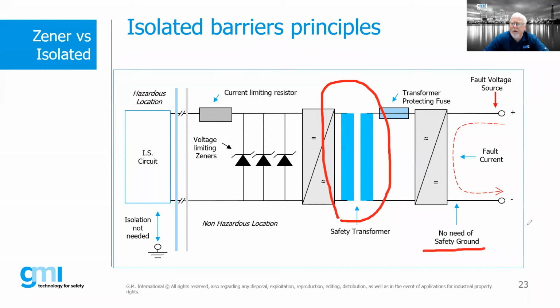Notice here, there is no need for a safety ground. We may need to ground our isolator onto just a DIN rail, a normal earth, but we do not have to have a dedicated safety ground for a galvanically isolated barrier.